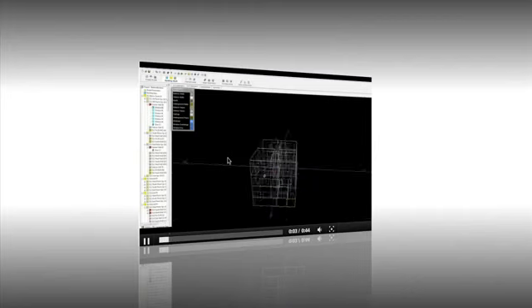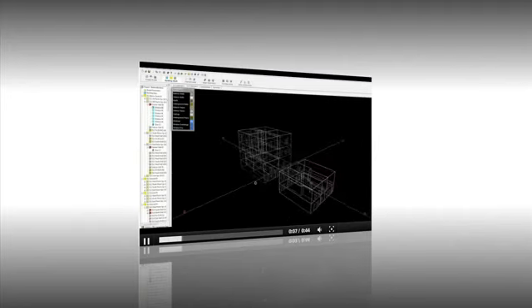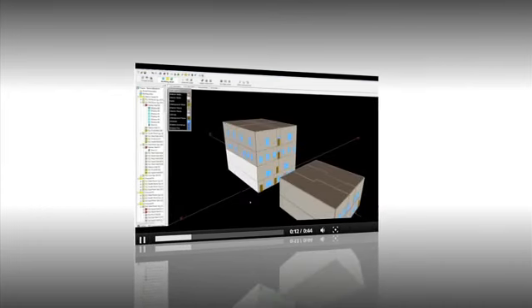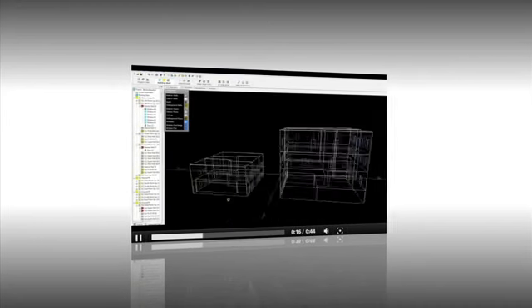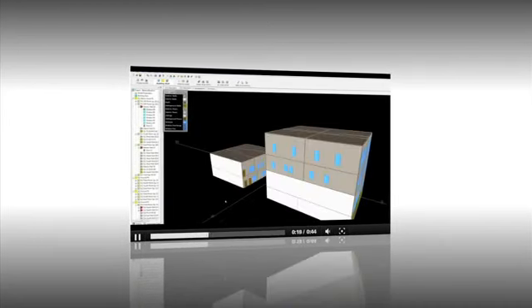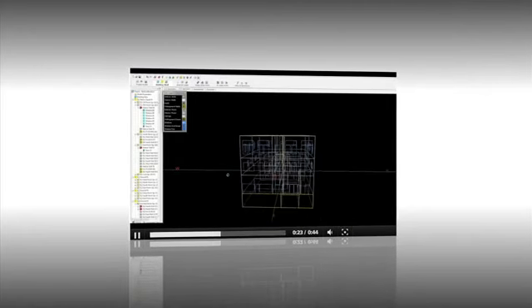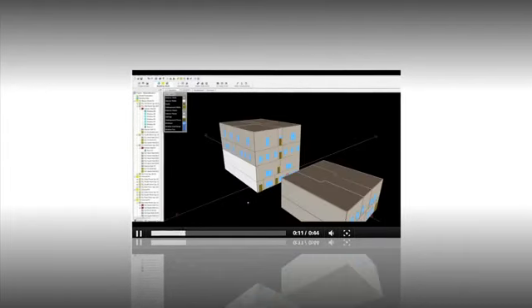Simulated performance typically requires an energy modeler to be involved. This approach looks at the entire building as fair game: light fixtures, insulation levels, mechanical efficiencies, etc. Simulated performance also could be referred to as a complex trade-off. For example, since the prescriptive code allows only up to 40% glass, you could trade up the efficiency of the mechanical systems to compensate for a higher percentage of glazing.